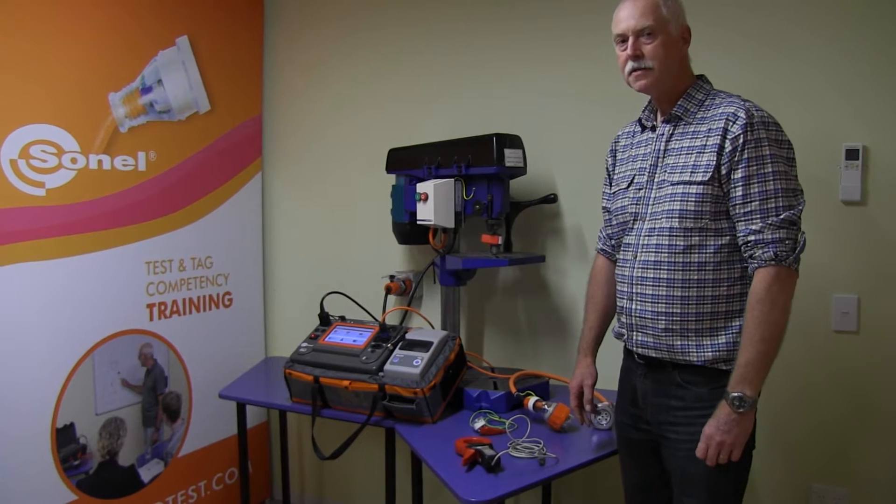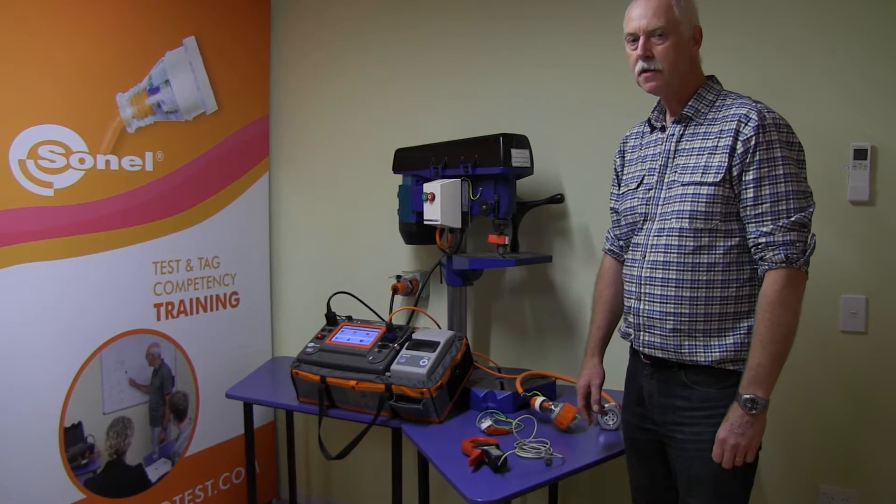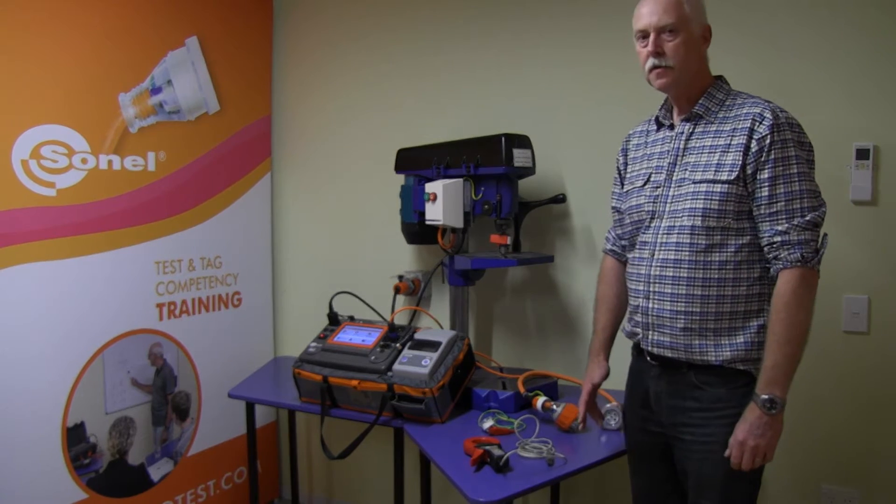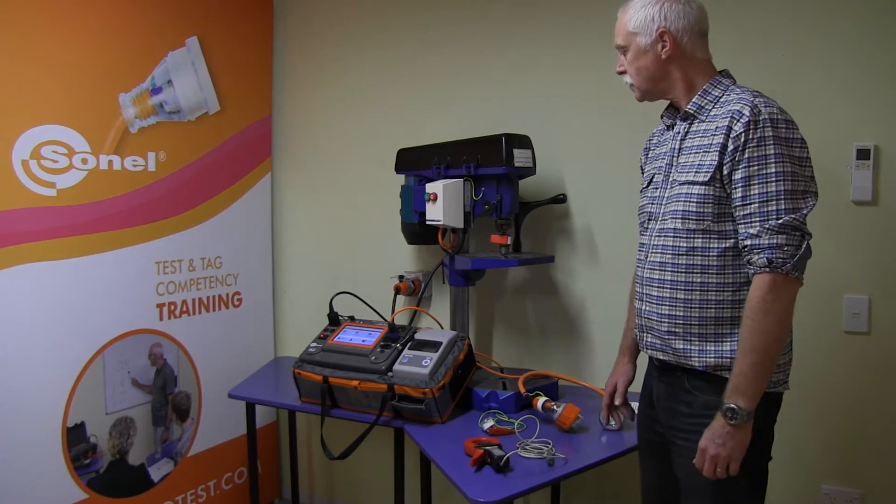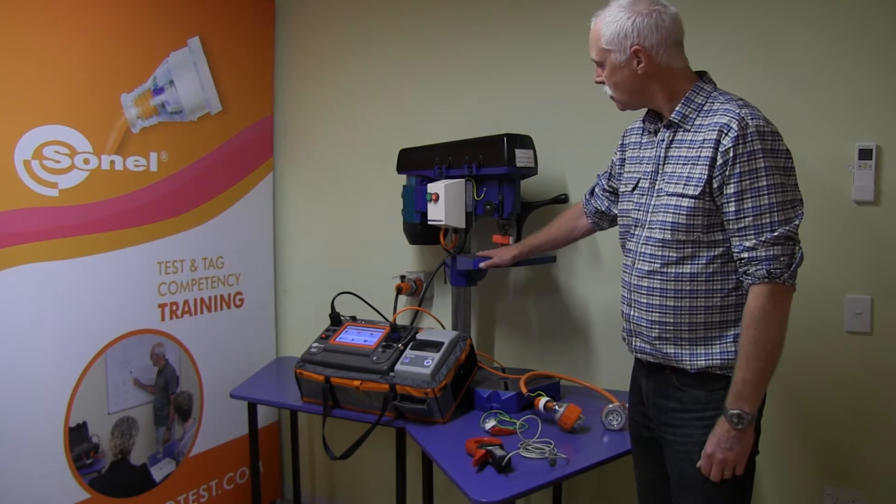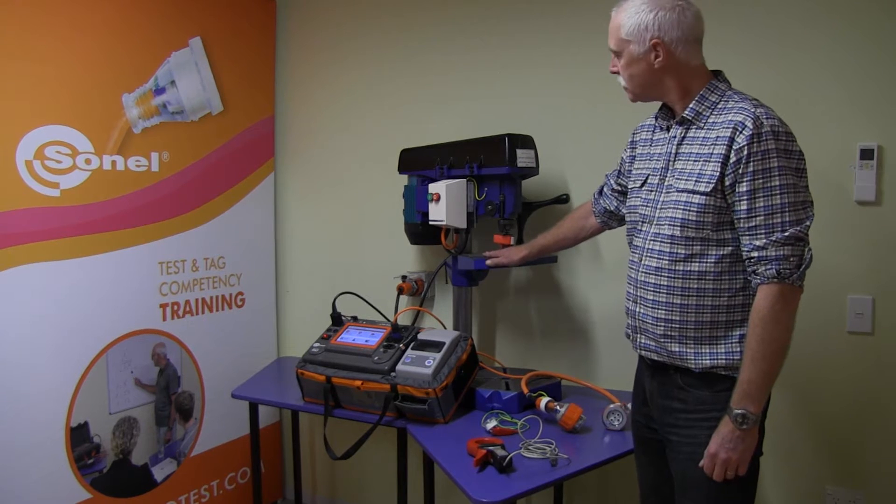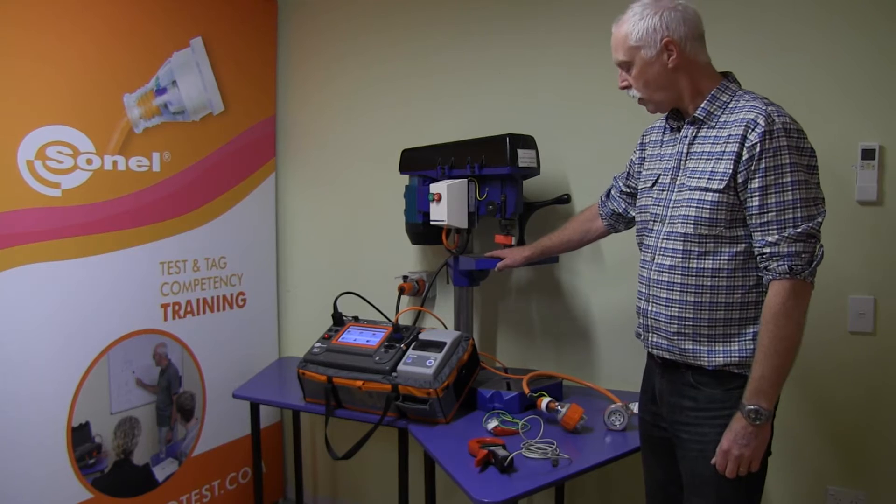I'm demonstrating how to test three-phase appliances in New Zealand or Australia in accordance with the 3760 standard. This standard requires a power-up leakage test on equipment like this. We cannot do an insulation test at 500 volts normally, so a leakage test is required.